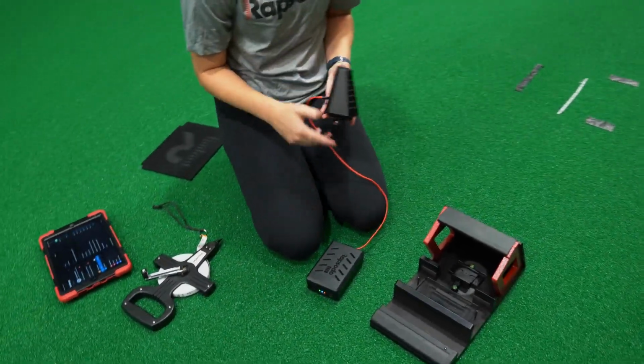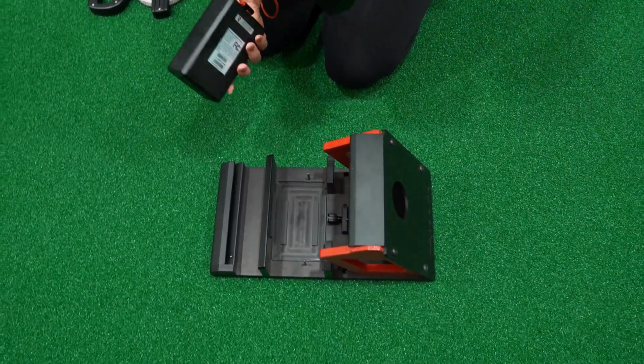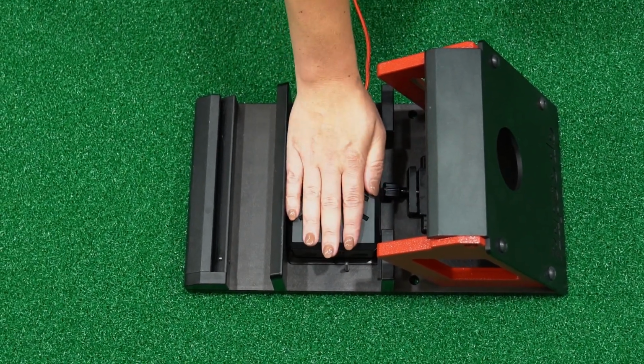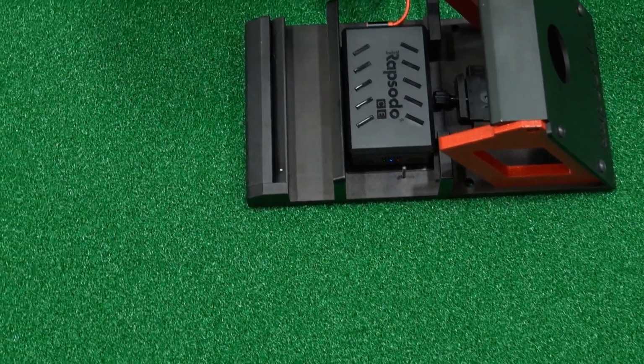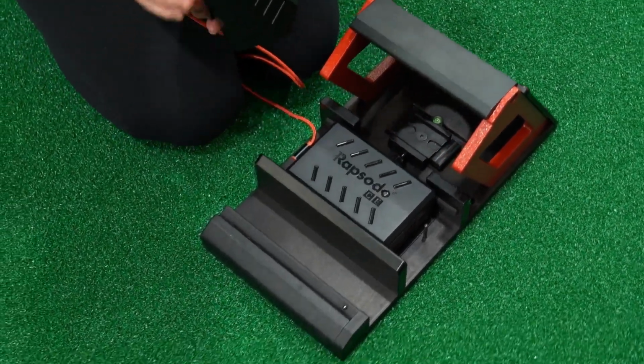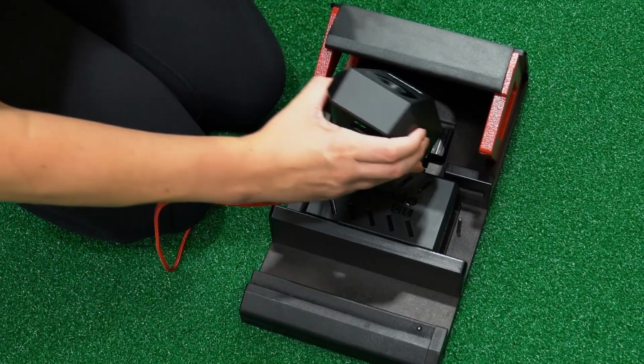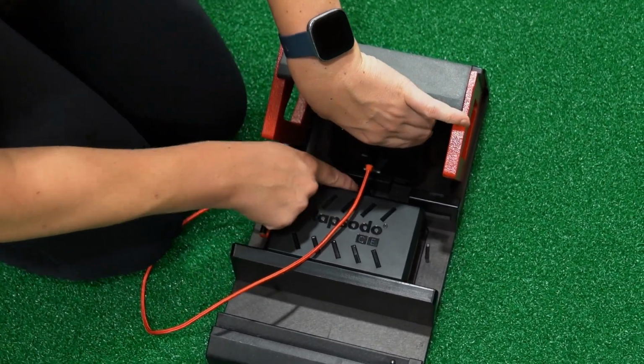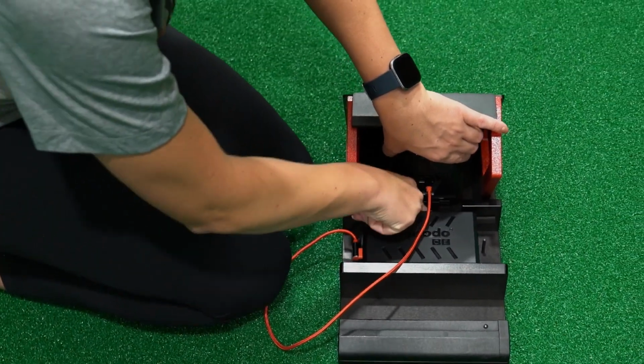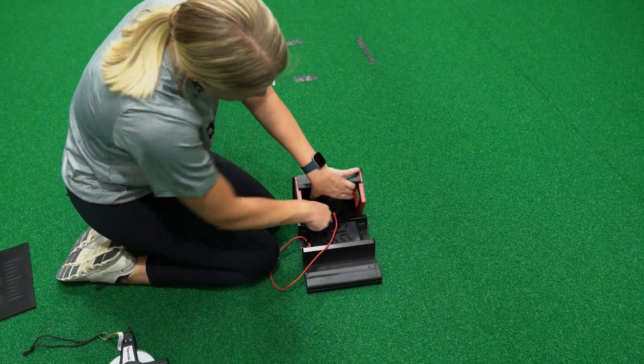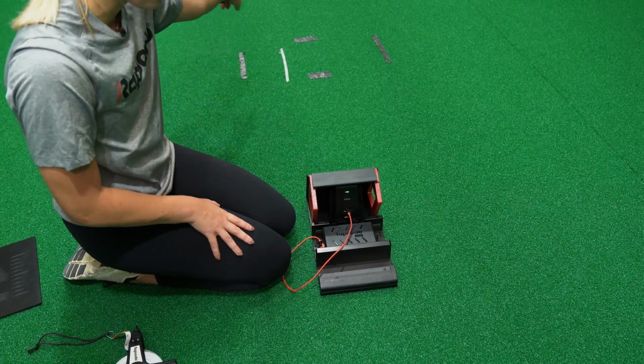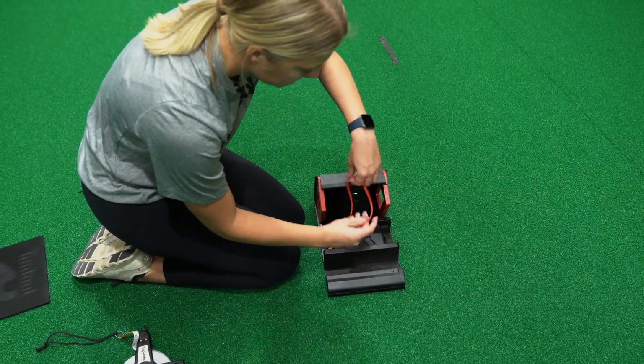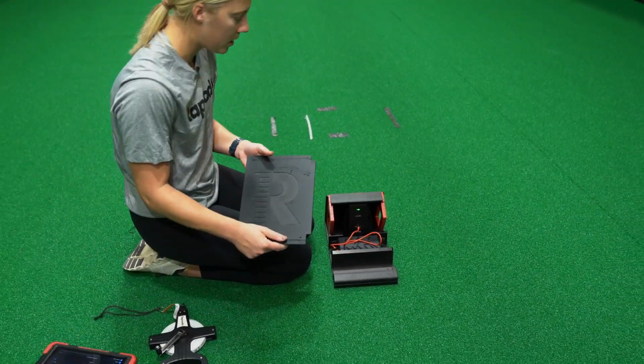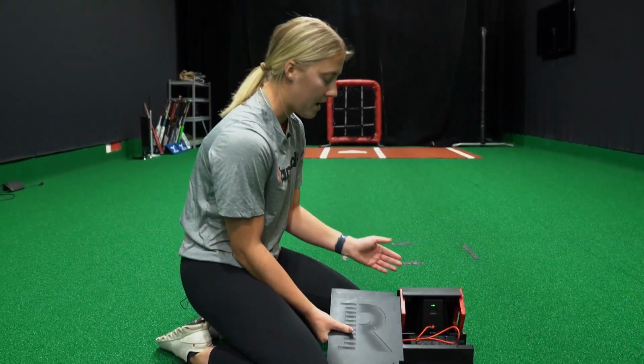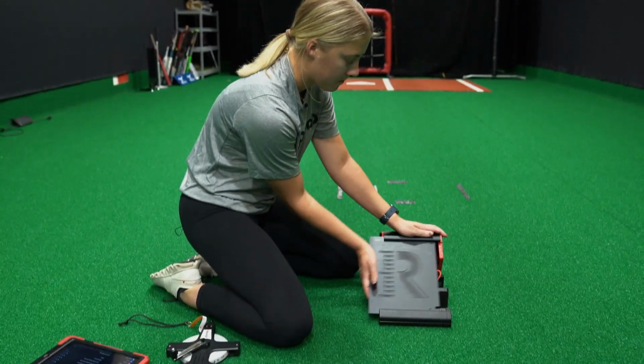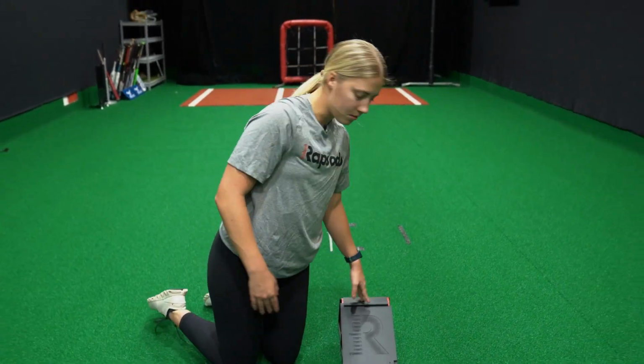So next we're going to place the technology inside of the tank. The RCE is going to be placed in here between the grooves. It fits nice right there. And then the monitor clip that we have here is going to go into this opening here. We have a dial that we want to loosen. That way you can slide in there and be as secure as possible. So we're going to slide that in. And then once we have it in there, we're going to tighten the dial. That way the monitor is nice and secure, doesn't move around, and then it should be centered looking out the hole in front of the tank. So this is good. And then we will slide the back plate over just for protection. You never want to use the units without the back plate on, just to keep it all safe. So that slides on. And for that, we are good to go now to grab the iPad.